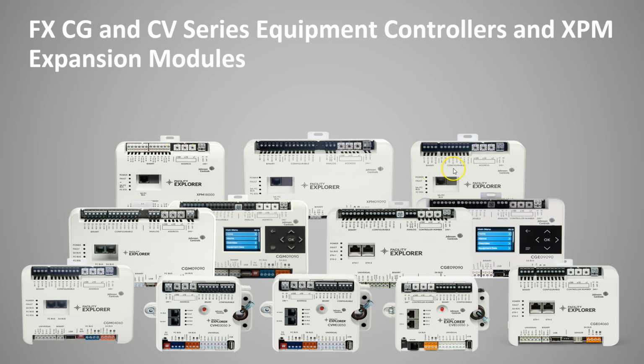Now, these expansion modules can be placed under the unitary controllers or the VAV controllers via the SA bus. And when you do that, they do not count as a device on your network. Actually, when you scan the JACE and these are underneath a controller, you will never see these.